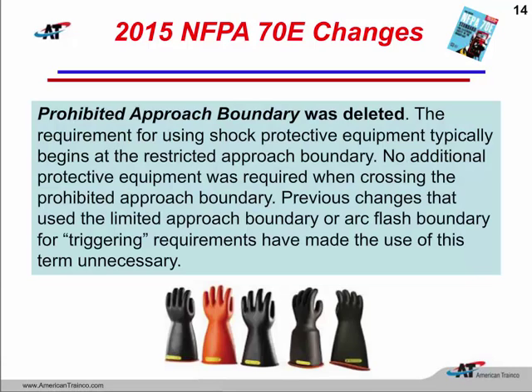The definition of prohibited approach boundary was deleted, and so that is a shock protection boundary. We had 3 shock protection boundaries in the 2012 edition of 70E, and they were a limited approach, which was the farthest one out, and then we had restricted, which started getting closer. The prohibited approach boundary actually was that we were making contact either with our meter or with a 1,000-volt rated tool. Well, the other 2 boundaries, they triggered something for us. The limited approach boundary triggered that no unqualified people could approach any closer than that distance, especially unless they were escorted by a qualified person.